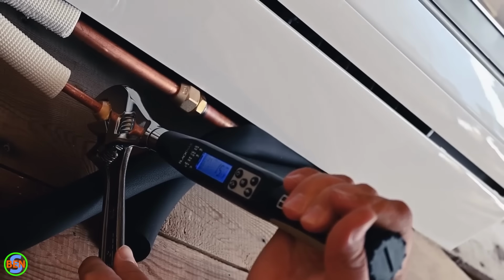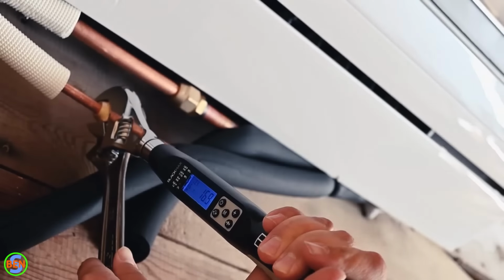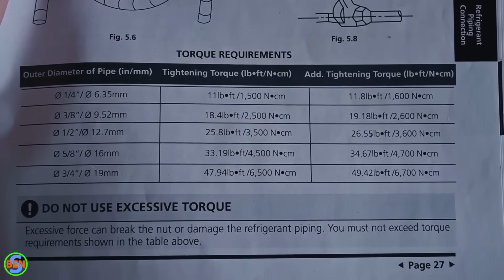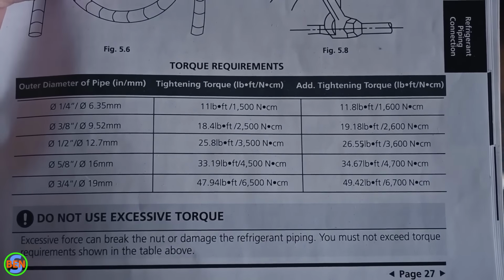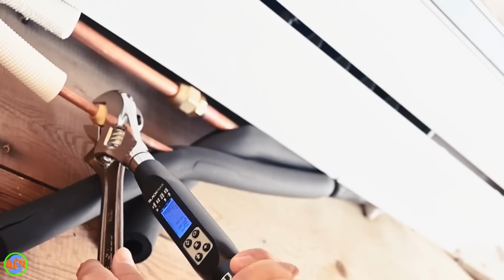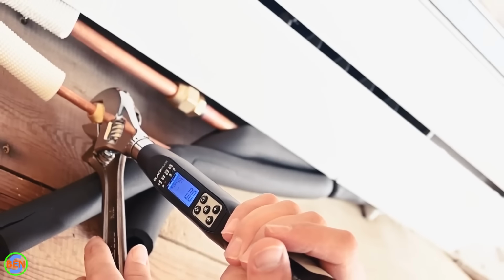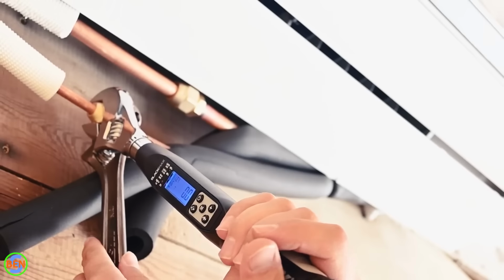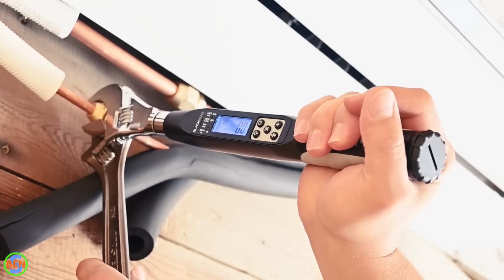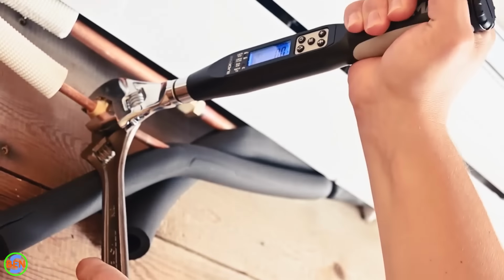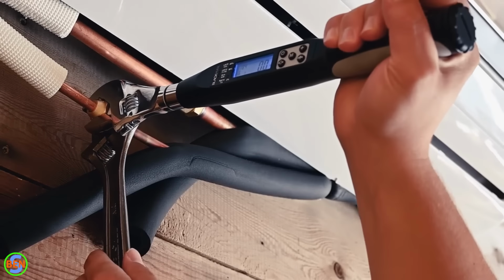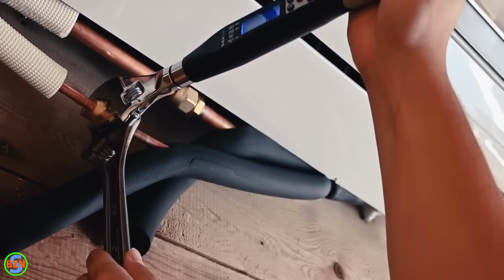Now when you tighten your connections, you're going to want to torque them down to the specified torque rating, which is located in the installation instructions. And when you do that, you want to torque it to the spec and then loosen it and then torque it again. And by connecting it twice like that, it really helps the flare just to conform to that fitting a little bit better and reduces the chances of you having a leak.